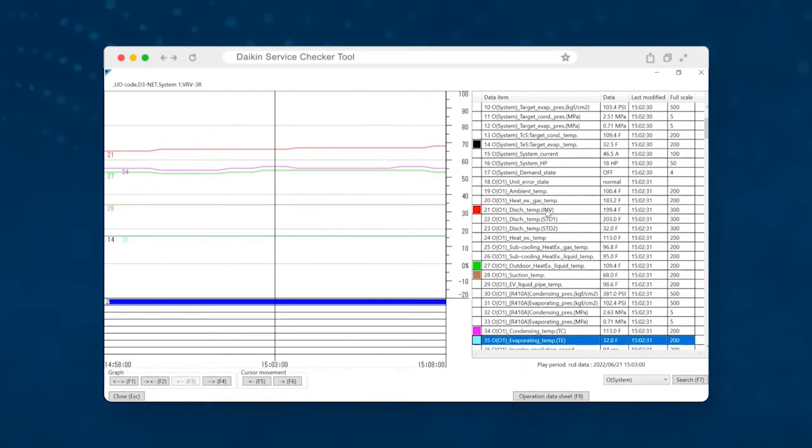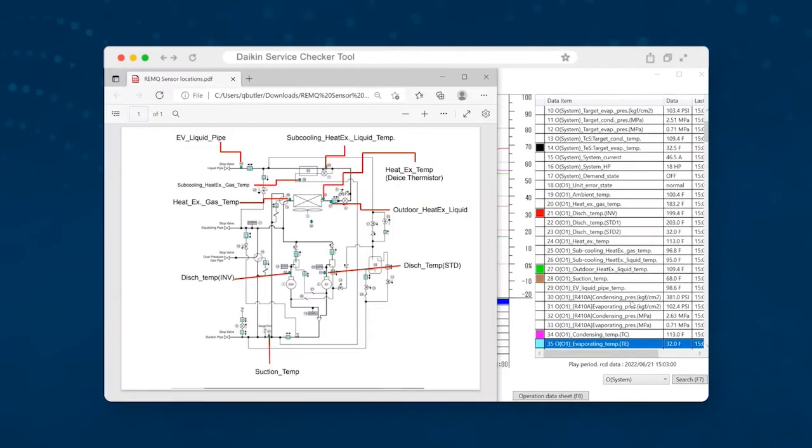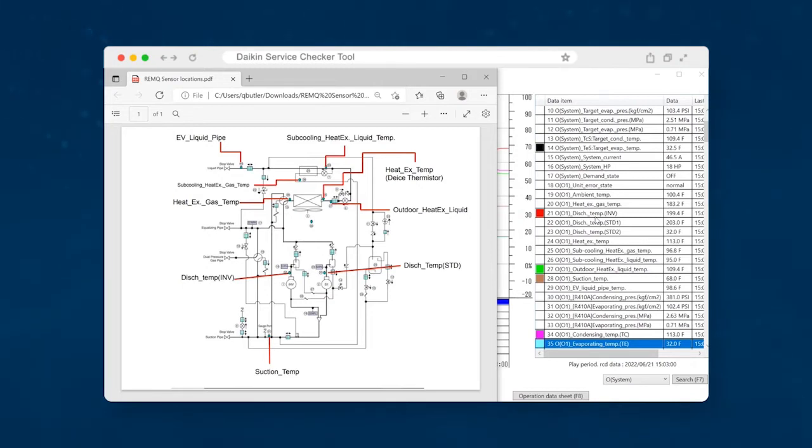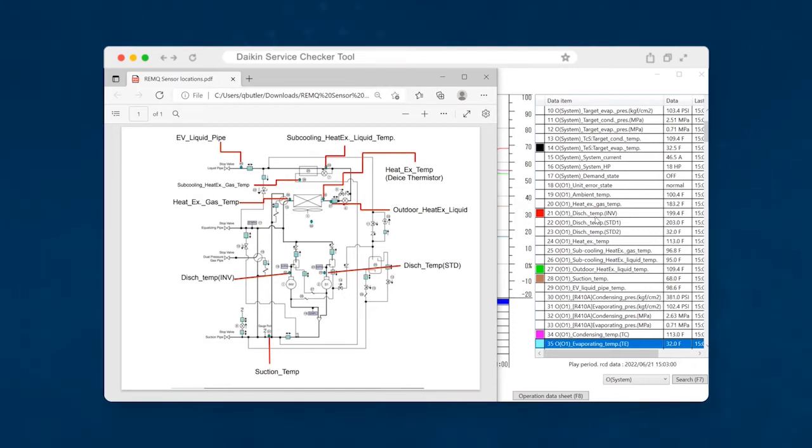The one piece that stands out that might be a little bit different to you is the discharge temp. So that's going to be a pipe temperature sensor that is located on the compressor. And so it's helpful if you can pull up your piping diagram. Now this is a very pertinent piece of information on the Daikin VRV system, as we can calculate what's called discharge superheat based off of this value. And so the first thing that I look at any time that I'm going to look at a VRV system and the health of the system is the discharge superheat, because it generally tells you the story.